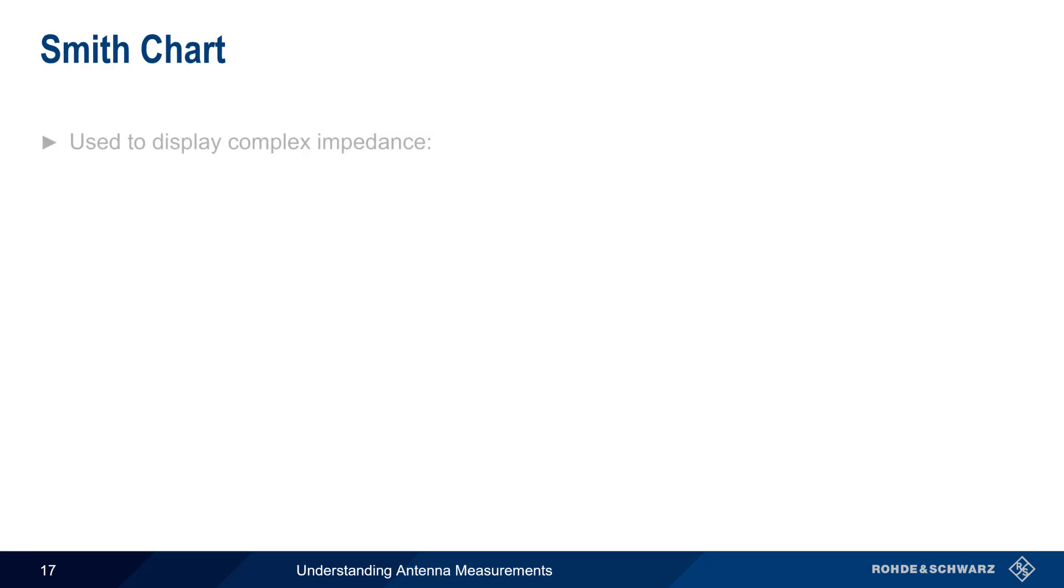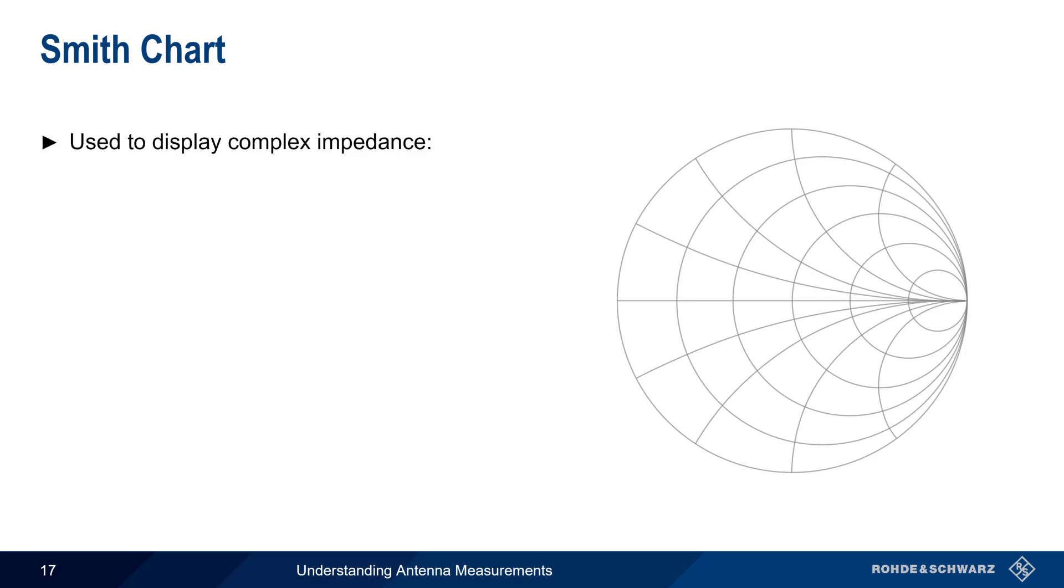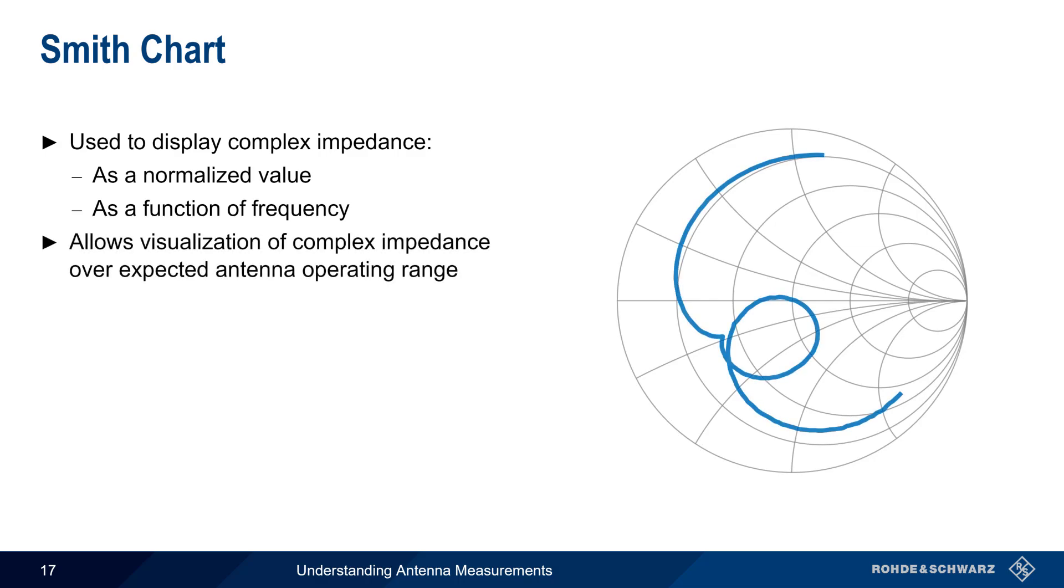On VNAs, complex impedance values are often displayed on a Smith chart. The Smith chart shows complex impedance as a normalized value and as a function of frequency. In the case of antenna testing, the Smith chart allows easy visualization of complex impedance over the measured frequency range, and markers can be used to read off the complex impedance at a given frequency.